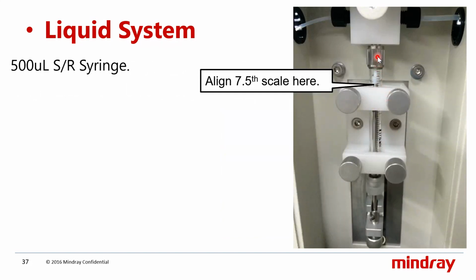And since this is the main syringe for sample and reagent, whenever you are replacing the syringe, you need to take care of this. This area should be exactly 7.5. Whenever you are fixing it, this area should be 7.5 bar on the scale.